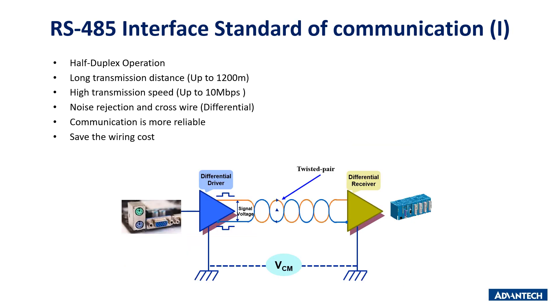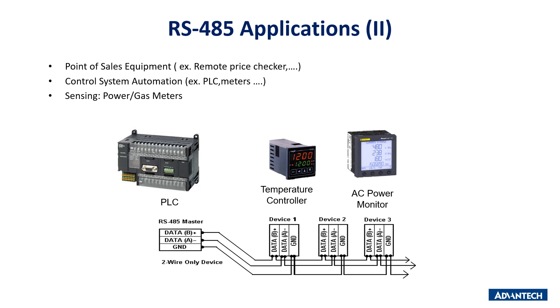For the RS-485 standard, it supports half duplex operation — it can send and receive data but not simultaneously. It has noise rejection using cross-wiring to reduce electromagnetic interference. It supports a long transmission distance up to 1,200 meters at a high transmission speed up to 10 megabits per second, and saves wiring cost because it uses only three wires. RS-485 is widely used in industrial environments including POS systems, automatic control systems, and sensing applications.